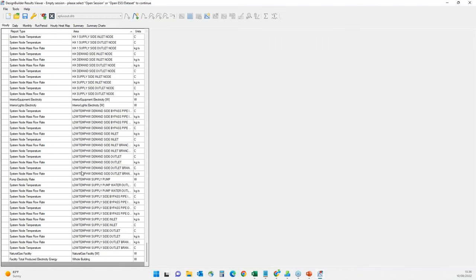The EMS script logic is: if grid carbon intensity is less than 0.2 kg CO2/kWh, or if water tank temperature goes below 50°C, then the boiler is on; otherwise it remains off. The last items are specific outputs I am requesting to check if the load shifting is working correctly. I'll press OK and run the simulation for the same settings, but with the surface outputs turned off to reduce the simulation result file size.